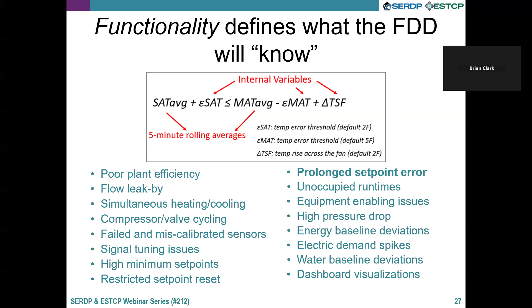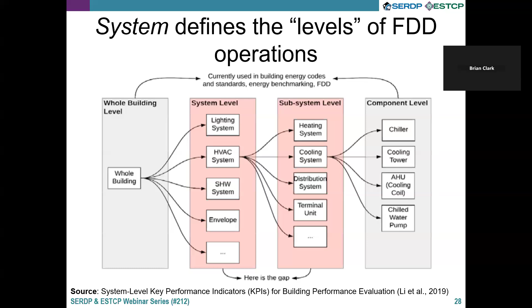System is another question. So, what are the levels that the FDD is operating at? Is it looking at certain components? Do we need to identify specific pieces of equipment in a building, as well as certain buildings? And then how are we aggregating some of those pieces of information? There's been some studies cited here that talk about key performance indicators that are missing in this aggregation chain. So identifying if you want to see certain things accumulated at certain levels, if you want to know what is the, oh boy, kW per 1,000 cubic feet per minute of supply air in all your buildings so you can compare them, those kind of KPIs would have to be conceived or discussed, procured, and so forth.